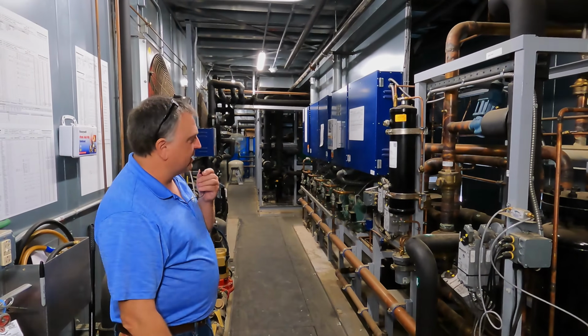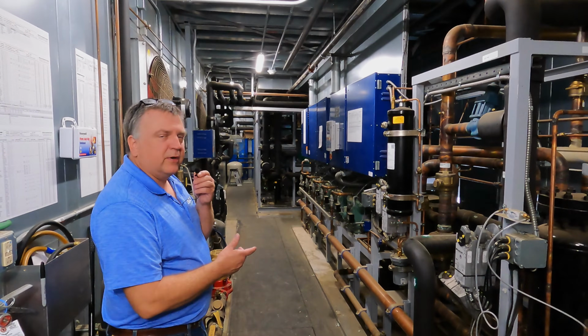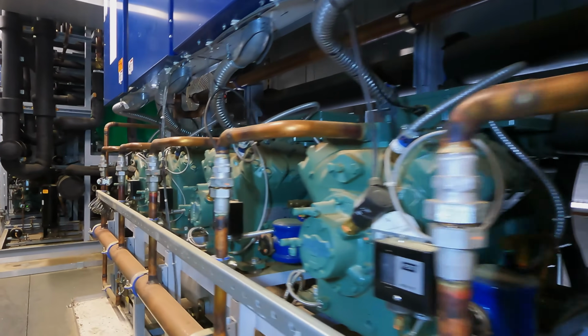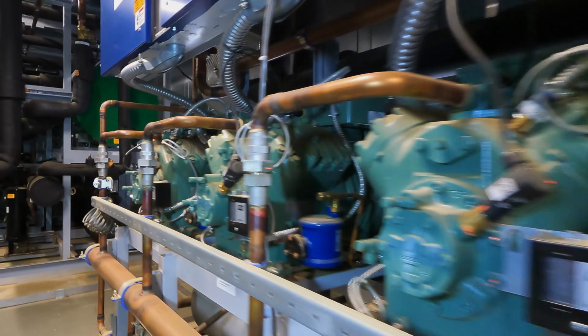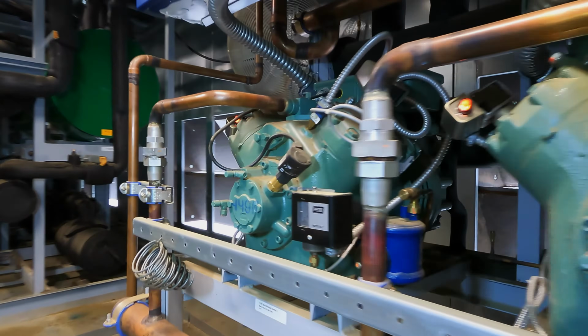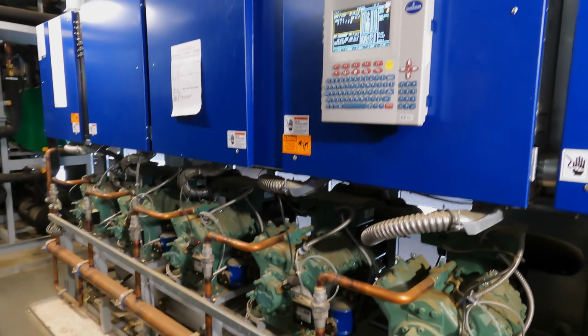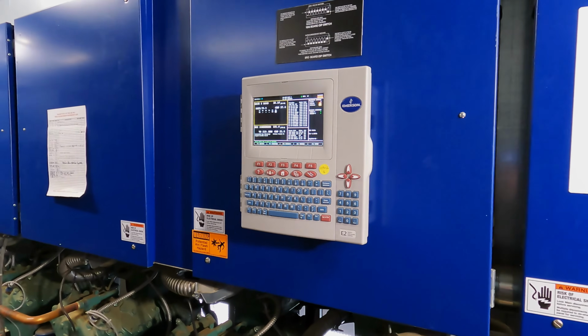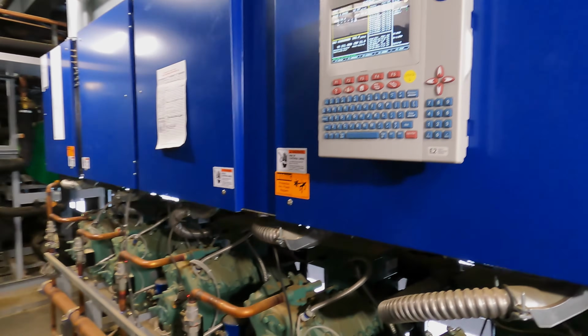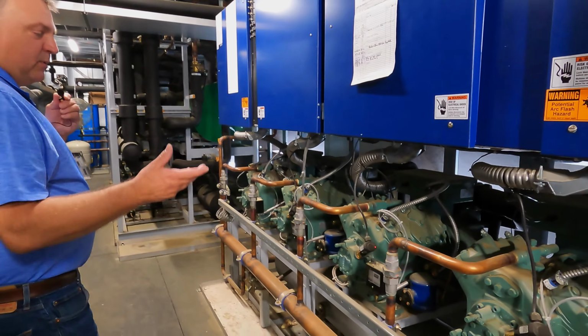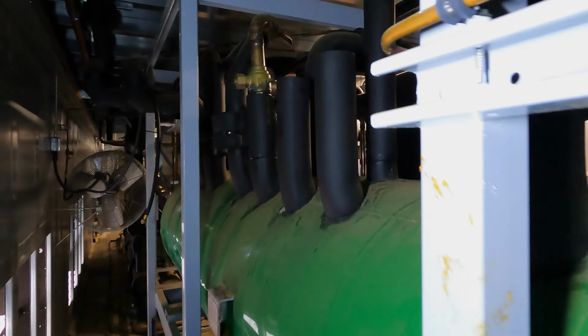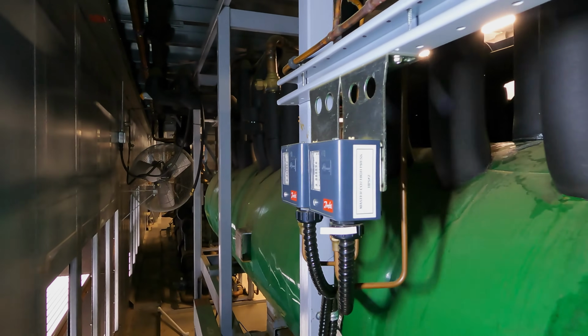Here, this is rack 2. This is the rack that we're using to change the CO2 vapor into a CO2 liquid, and that's what we're using to circulate through the store. We have an Emerson E2 controller running all this equipment. So what we're doing here is we're using this rack to chill the CO2 to get it to a liquid state so that we can put it down in the store at a safe pressure.